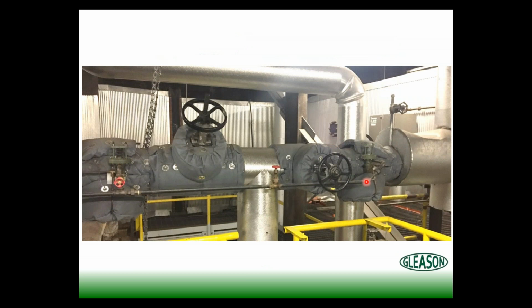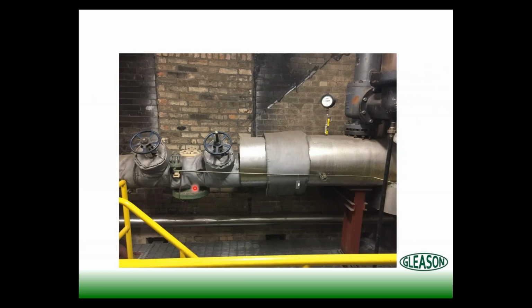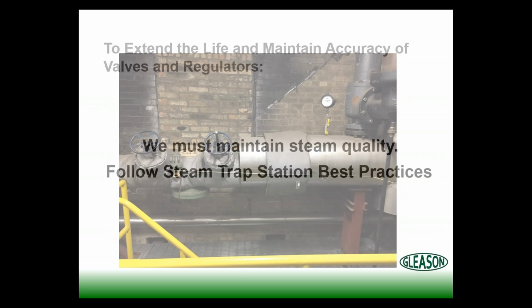Two more quick things on this. Notice here, they've insulated the bell. These are regulators. They've insulated the bell. We do not insulate the bell. We leave the bell uninsulated because we want condensate there in the diaphragm chamber or that diaphragm bell area because it gives a much more accurate regulation because the condensate is not compressible. So just another tip there.